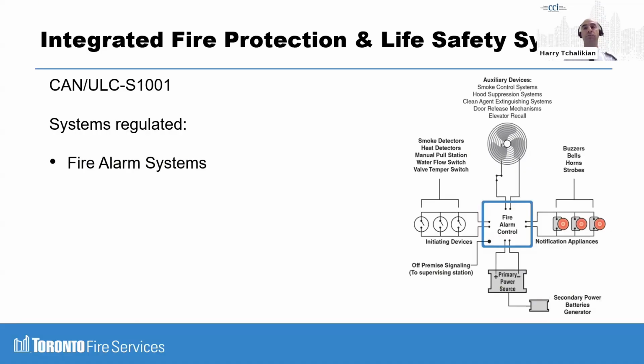The fire alarm system is the centerpiece of this requirement. A fire alarm system is comprised of your control unit, your initiating devices like smoke detectors and pull stations, your notification appliances like your bells, primary source, secondary power source, and you also have your auxiliary devices. And here's where CAN/ULC-S1001 comes into effect. So where your annual CAN/ULC-S536 inspection, testing and maintenance requirement ended, it ended here at the relay from the fire alarm system to the other system that it caused an input or output. And that's just a regular 24-volt, normally open, normally closed relay.